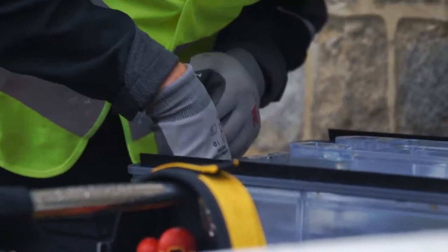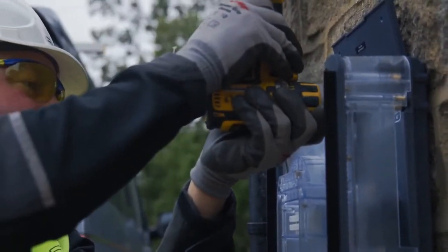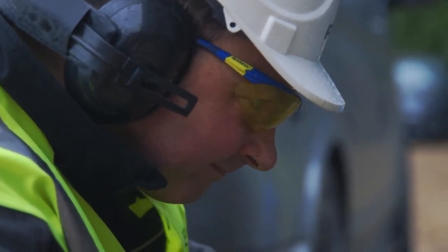So I also believe the Andersen unit's got the facilities to put a current transformer in there as well. So why would you want to do that? Yeah, so the Andersen A2 has adaptive loading, and this is designed basically to sense from the incoming supply, detect a level of loading on the supply, and if need be, it will act as a fail-safe mechanism. With the car being under constant charge, if it needs to, it will derate from, for example on a 7.2 kilowatt charger, from 32 amp all the way down to, I think it's somewhere around 3-4 amps, if need be. Okay, so that's if someone installed an electric shower, or they've got a high load in the house and they suddenly start using all their appliances, it makes sure you're not going to blow that service fuse.